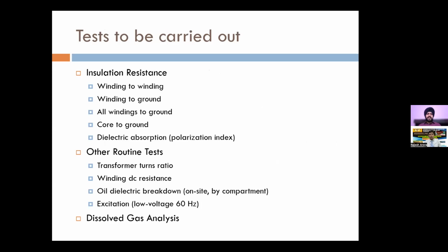These are just some of the tests that we mostly carry out. The most important is the one at the last, dissolved gas analysis, then the IR test, insulation resistance test, then other routine tests like turn ratio for a transformer. It is not relevant for a reactor. Then DC resistance, then oil test also. It can help you identify whether there is any issue with moisture ingress in the transformer, but this is relevant more during our routine maintenance.